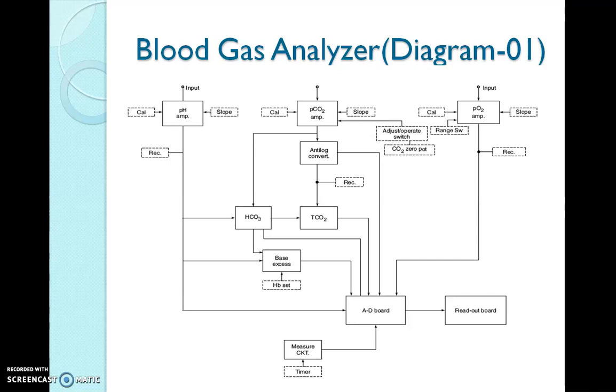In this blood gas analyzer, the vacuum system provides aspiration and flushing services for all 3 electrodes. Calibrating gases are selected by a special push button control and passed through the sample chamber whenever required. Two gases of accurately known O2 and CO2 percentages are required for calibrating the analyzer in the PO2 and PCO2 modes.